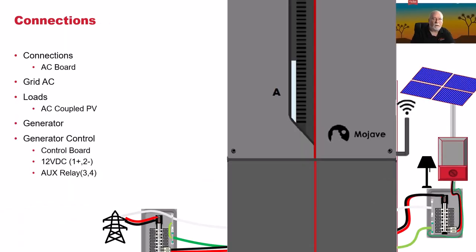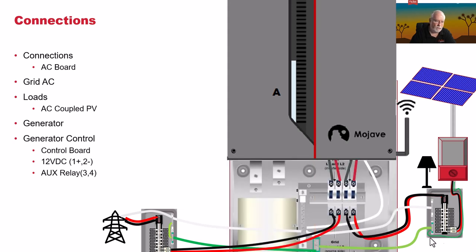On this next slide, we're going to connect up all the items, walk through and show you where each connection is and how it works. So first thing I'm going to do is drop the front cover on the unit, exposing the inside connections. And as you see from the power line, we have our neutral, which comes from the transformer. It's bonded in our cabinet. Then we take our neutral over and attach it to our neutral in our Mojave. There's one neutral line that goes up to the inverter. The other one goes to the other backup loads panel. And that backup loads panel then services all of the split phase loads here.